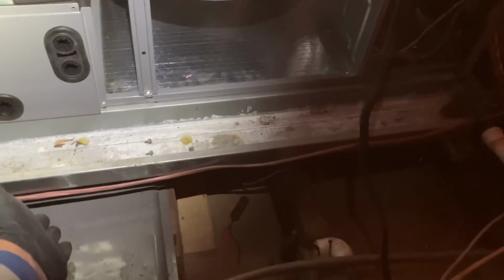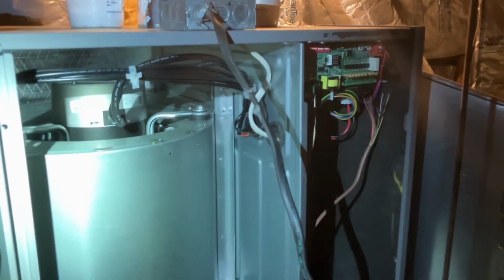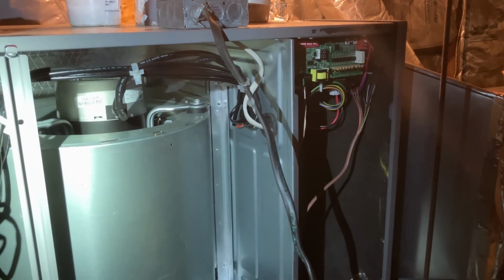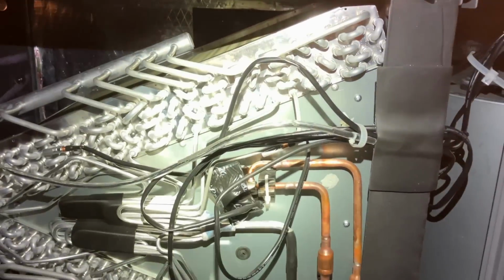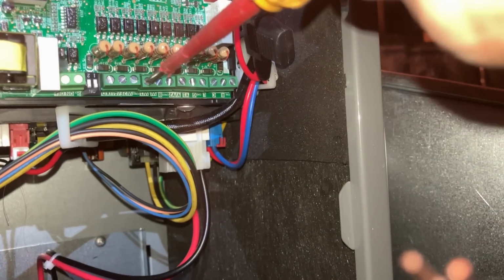Unfortunately, the budget doesn't allow it. In this case, where we're using the existing emergency drain pan, we are going to be working on this duct work. It's old duct board right now. It's literally falling apart. But what's great about the Senville is that it compensates CFM based on ductwork. Awesome. Awesome feature. All right, so I'm about to start the low voltage wiring here.